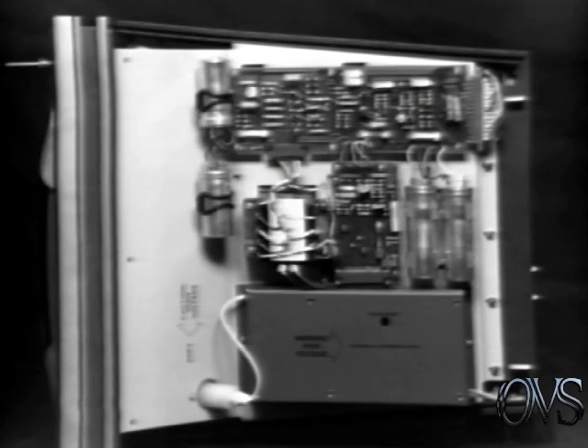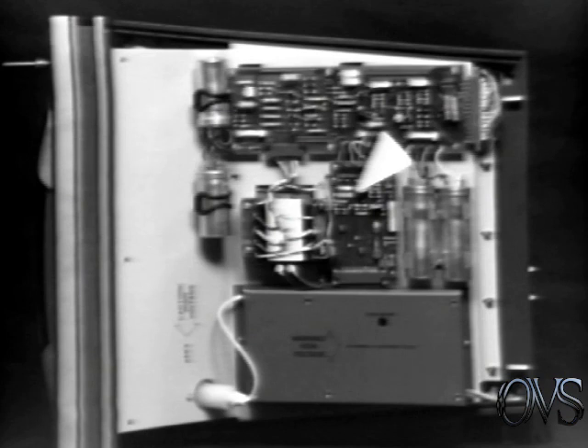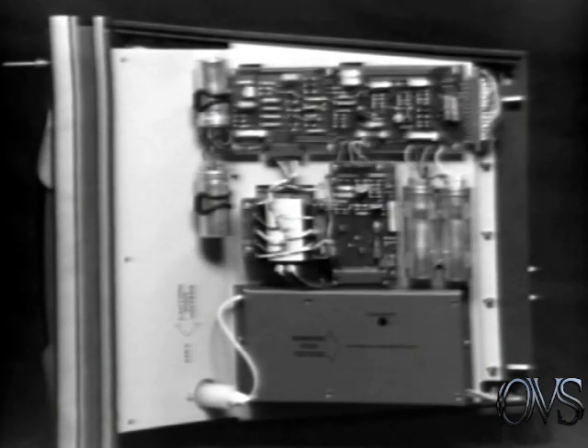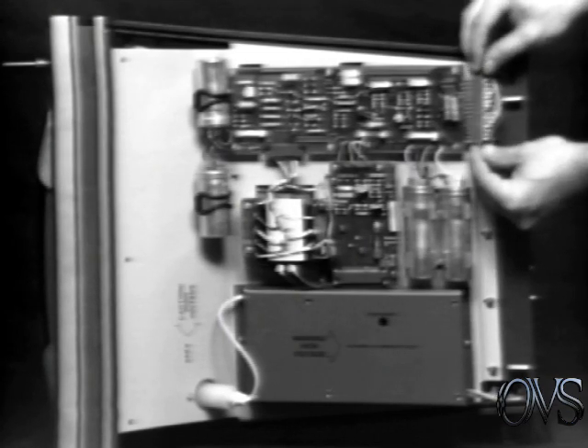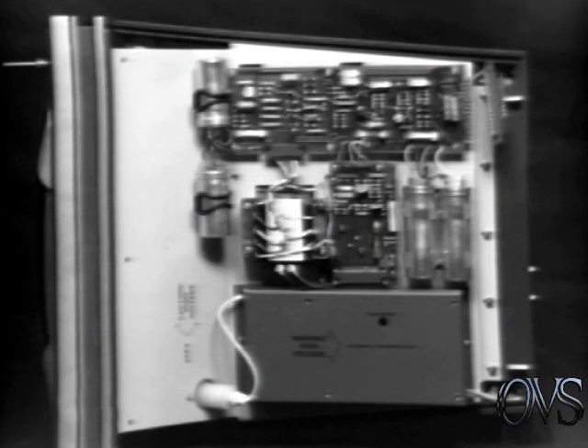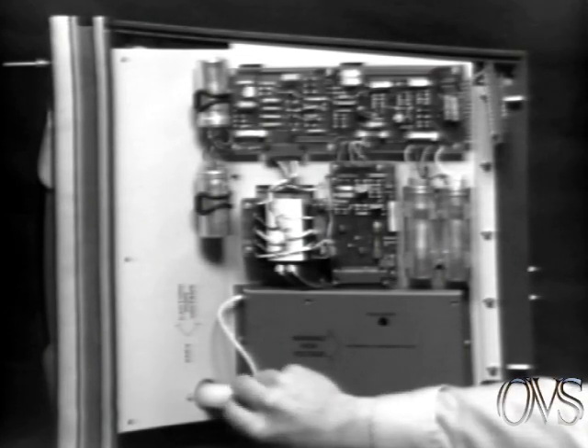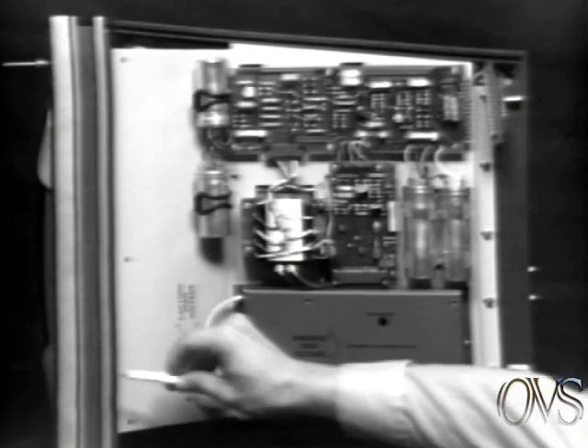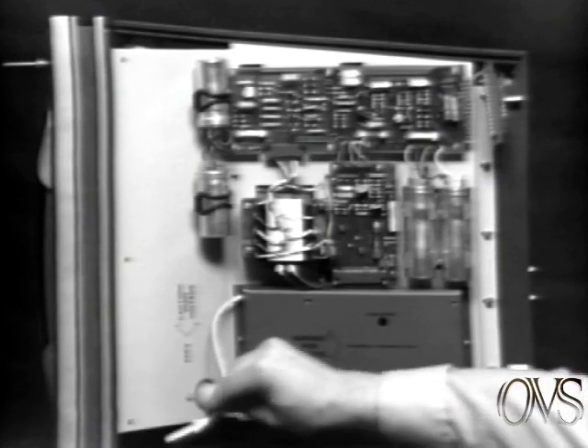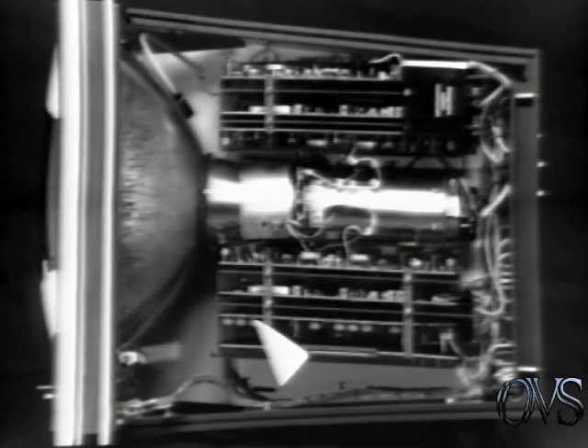The bottom side of the instrument exposes the low voltage power supply, high voltage regulator, and high voltage rectifier. Notice that most board connections are made with edge connectors, permitting convenient board removal. Here's the CRT post-accelerator connector. Anytime this is disconnected, it should be discharged to ground immediately as a safety precaution. All other circuitry is located on the top side: Z-axis amplifier, Y-axis input, Y-axis output, X-axis input, X-axis output, and focus astigmatism board. An extender board is also provided.